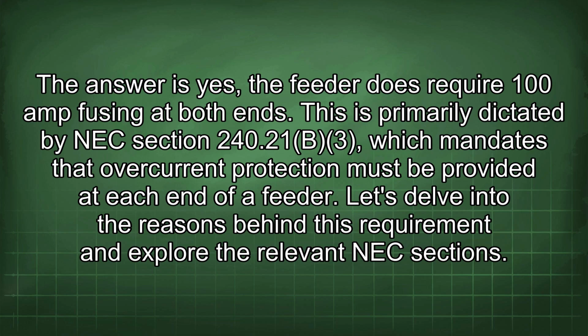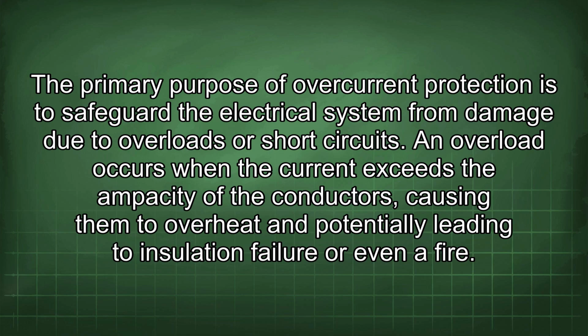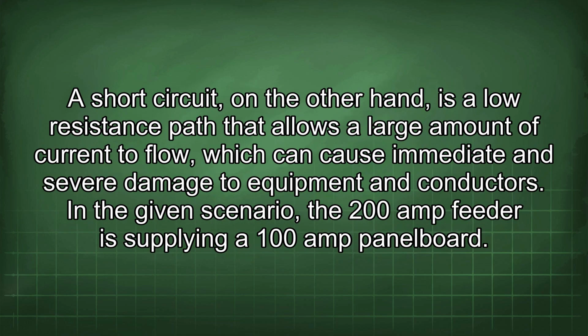This is primarily dictated by NEC Section 240.21b3, which mandates that overcurrent protection must be provided at each end of a feeder. Let's delve into the reasons behind this requirement and explore the relevant NEC sections. The primary purpose of overcurrent protection is to safeguard the electrical system from damage due to overloads or short circuits. An overload occurs when the current exceeds the ampacity of the conductors, causing them to overheat and potentially leading to insulation failure or even a fire. A short circuit, on the other hand, is a low resistance path that allows a large amount of current to flow, which can cause immediate and severe damage to equipment and conductors.